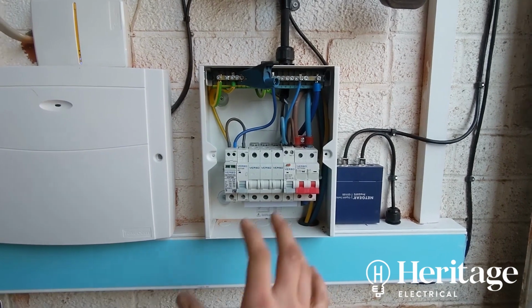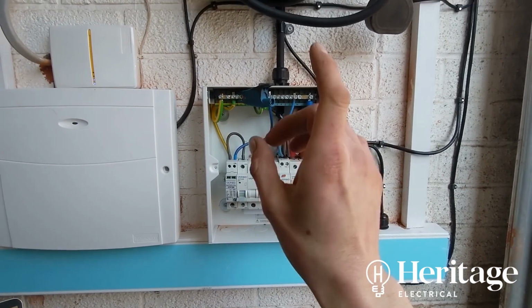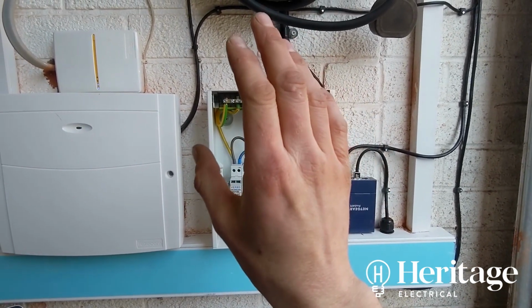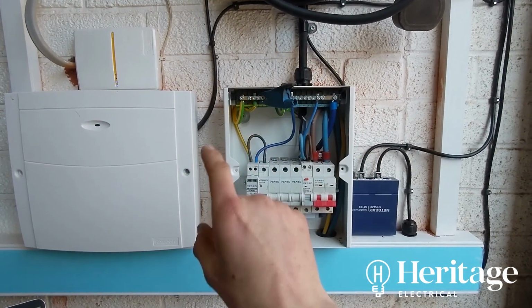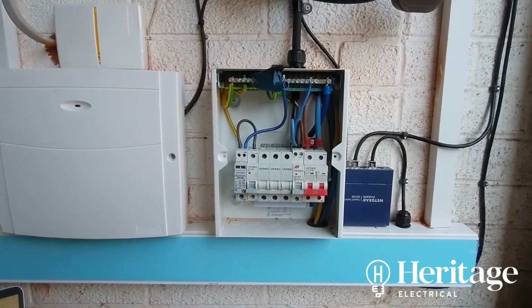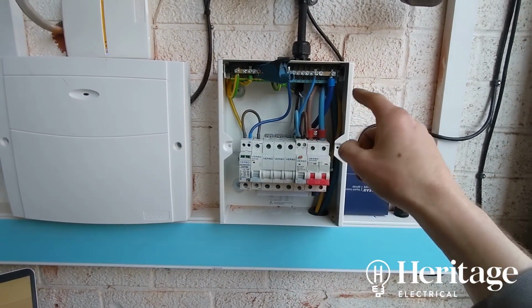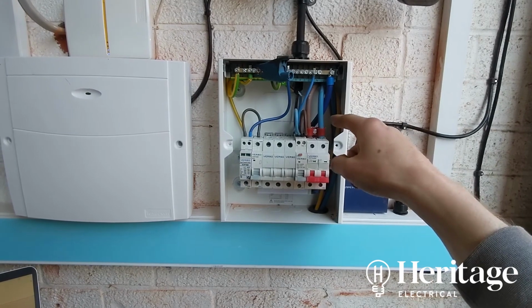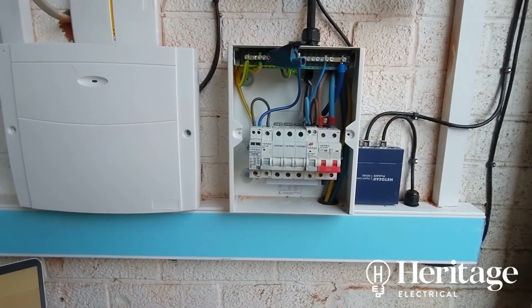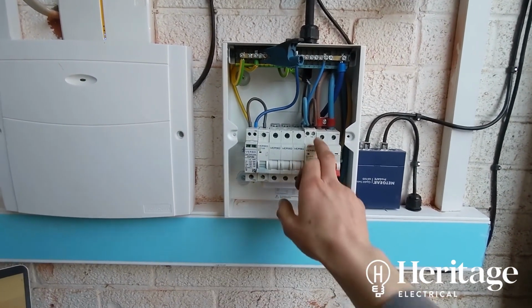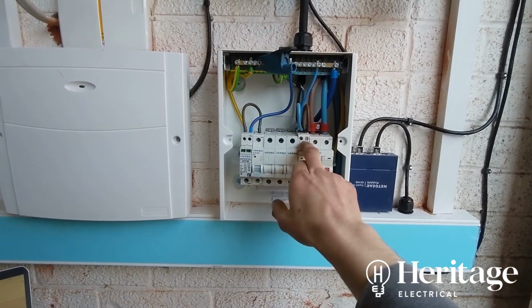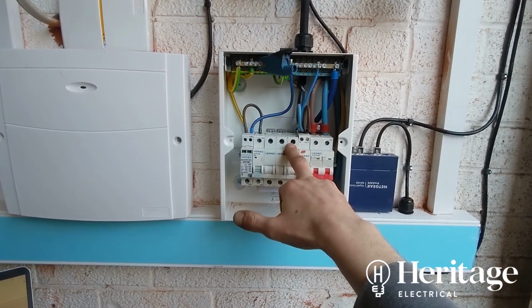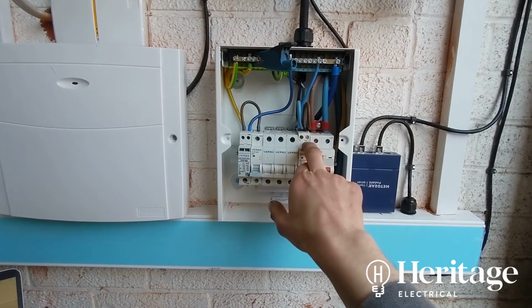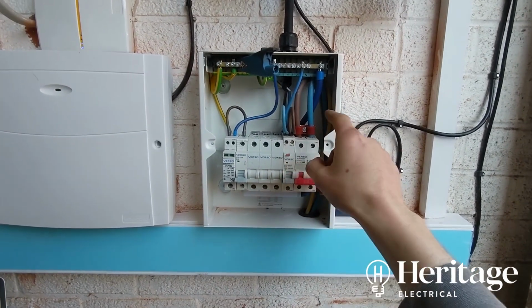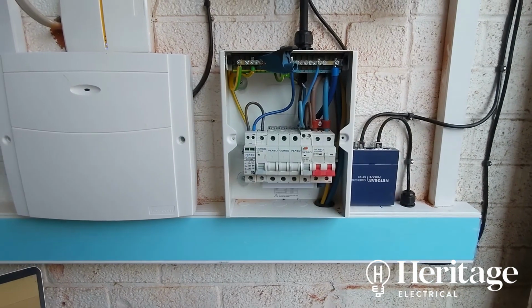So then, just had a quick thought. So we've got a 1361 fuse protecting the tails. So we've not used 25mm tails, we've just used 16mm tails here because, you know, we've got a 32 amp car charger, and then we're going to have a solar array, which might just take us over the capacity for 10mm tails, so we've bumped it up to 16 just in case.